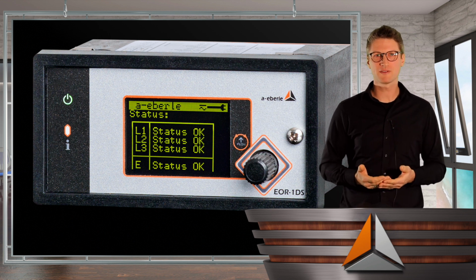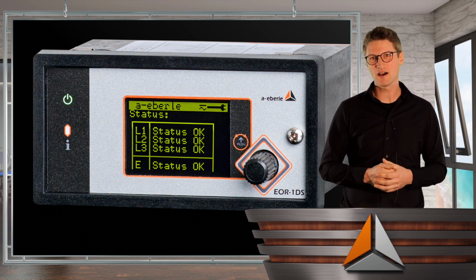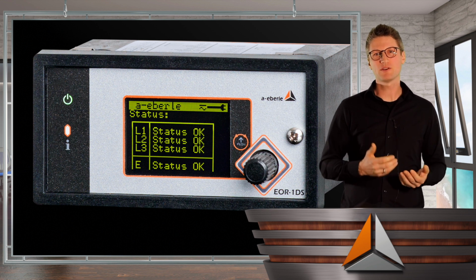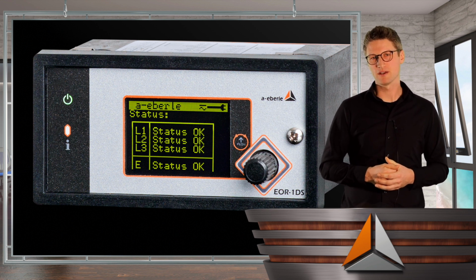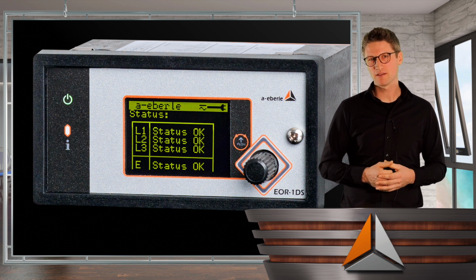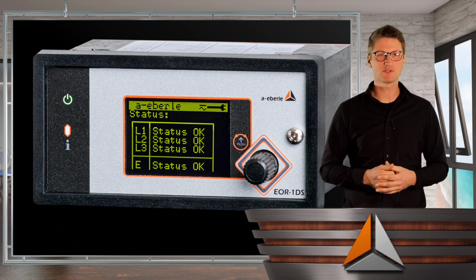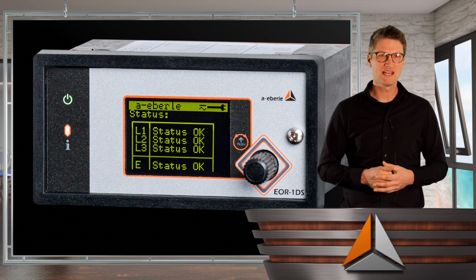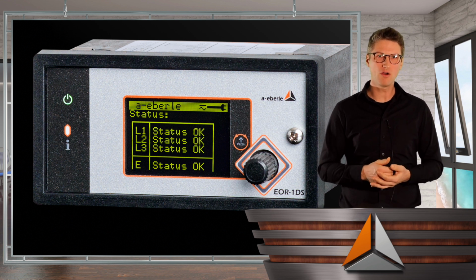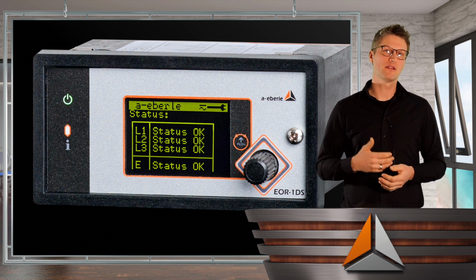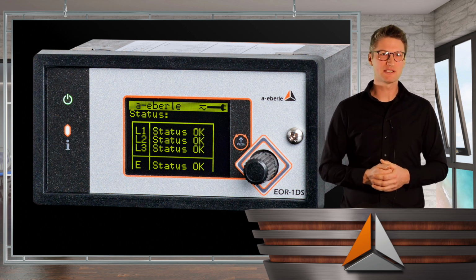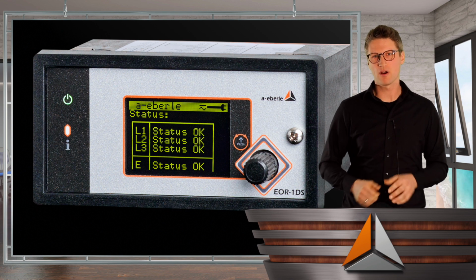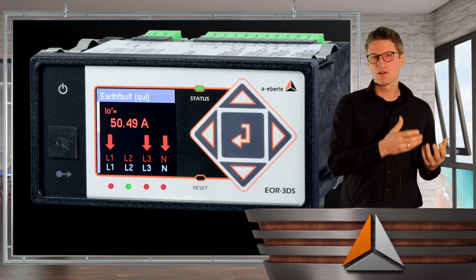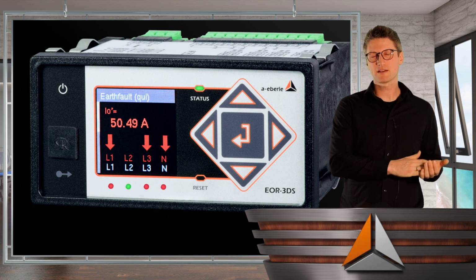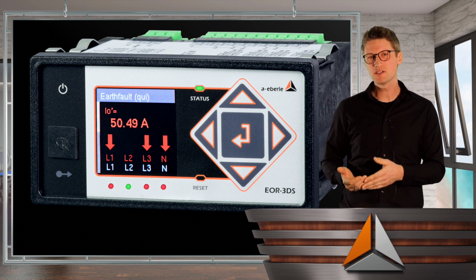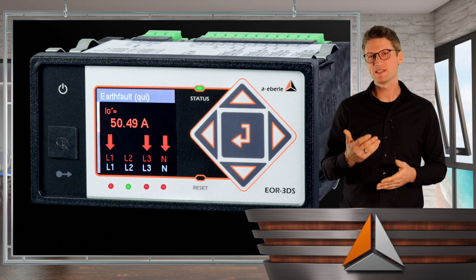Yeah, here the main features in overview I want to emphasize, especially the possibility of fault records and logbooks that are saved on an internal SD card, and a wide range power supply of the device. So you can supply the device AC and DC up to 260 volts. In addition, the device has an internal long life capacitor installed where the indication of the device is guaranteed for at least 4 hours.